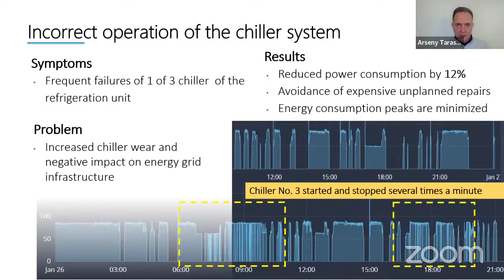By fixing this, the company managed to reduce energy consumption by 12%. But what's also very important is they avoided very expensive and unplanned repairs of chiller number 3, which had always been an issue they couldn't understand. The issue, as we identified, was that the automation was programmed incorrectly from the very beginning. So for several years, this was an issue they couldn't understand the reason for. That's the first example.